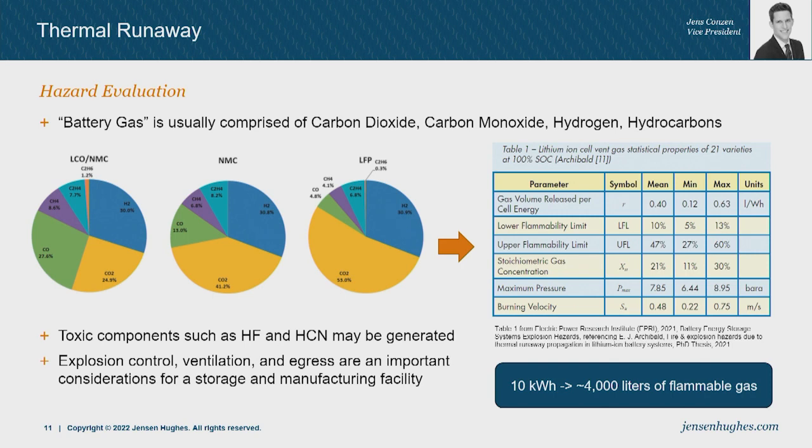So I put this table in here, which is from an EPRI paper that was referencing a dissertation from a recent PhD student. He performed 21 different tests and captured that data. RISE in Sweden actually came out with a new paper just last month with a much larger series of tests, pretty much confirming this table. But basically, it means there's a mean value of 0.4 liters per watt hour.